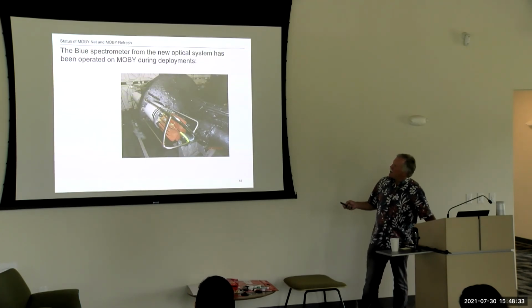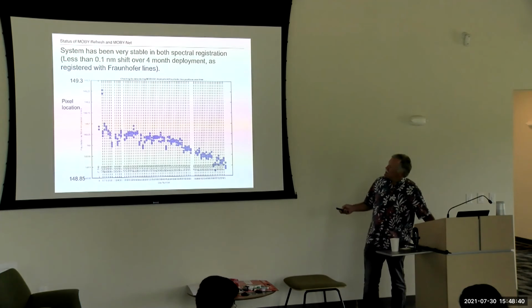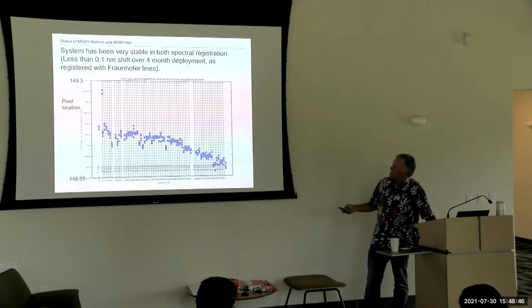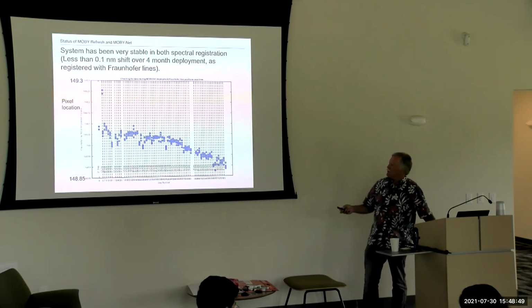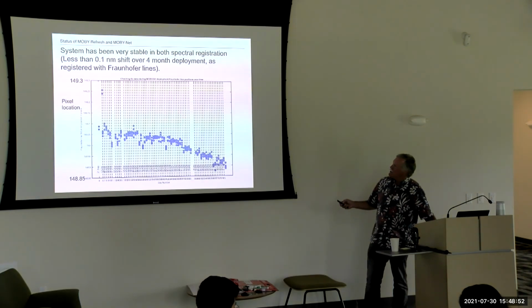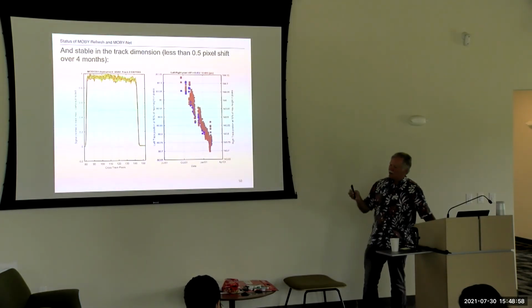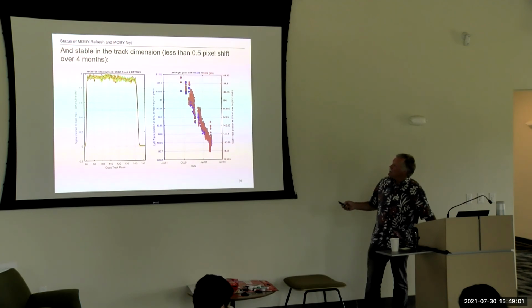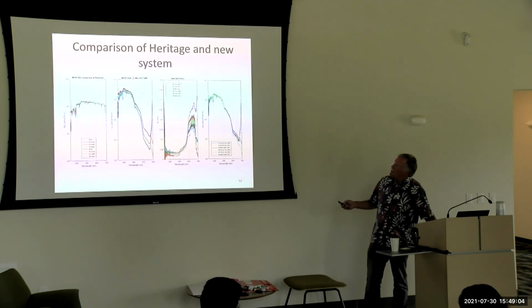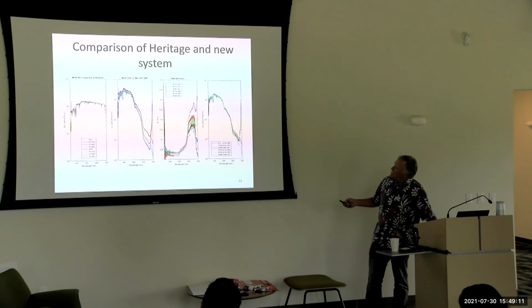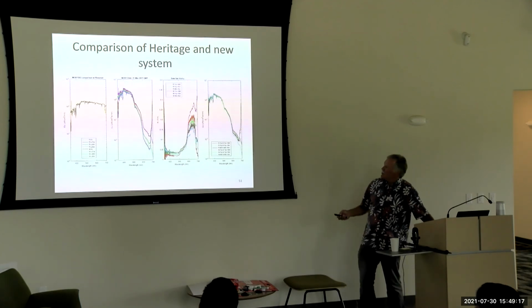We've tested the blue spectrometer a lot at sea by putting it alongside the Moby buoy at the bottom and making simultaneous measurements. The system is stable, and we can look at Fraunhofer lines. We have such high resolution that we can measure the spectral calibration with the Fraunhofer lines, and it shifted less than 1/10 of a nanometer over a 4-month deployment, which is good. Each of those tracks was very stable over deployment. So we've been able to test a lot of stability. Here's a comparison between the heritage system and the new one. This is the water leaving radiance, where Moby is M and the new system is R. It works well. Here's ES.